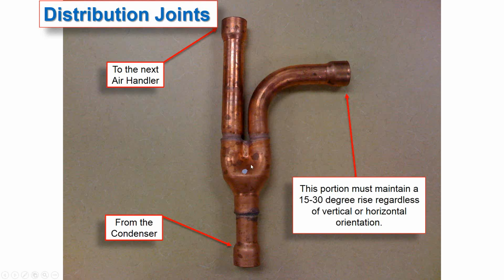And we want to position these joints at a 15 to 30 degree angle, meaning that this end would be up 15 to 30 degrees for proper refrigerant flow through this joint. So that's the orientation we're looking for, is 15 to 30 degrees.